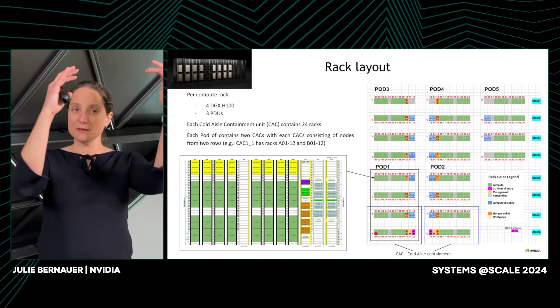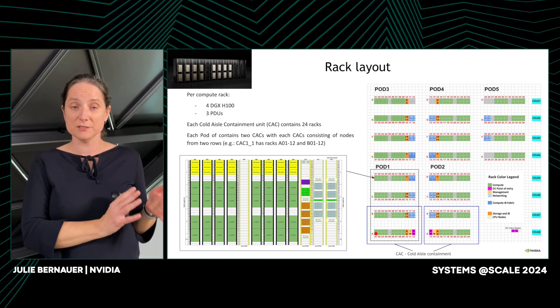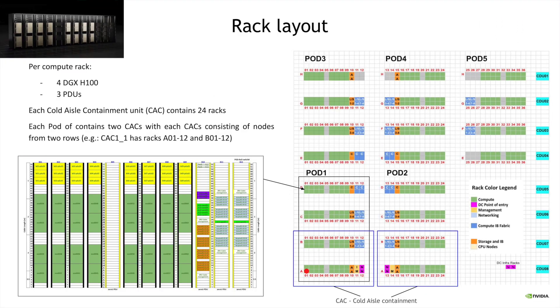To scale the system, we take four servers and put them in a rack using three PDUs, then keep duplicating. We have eight racks of four DGX each in a row — 12 total with management and storage. Two rows are placed in a cold aisle containment system (CAC), which controls the thermal environment to keep GPUs cool and ensure performance. We stack CACs to form a pod, which is the basic unit of the super pod and can run on its own.